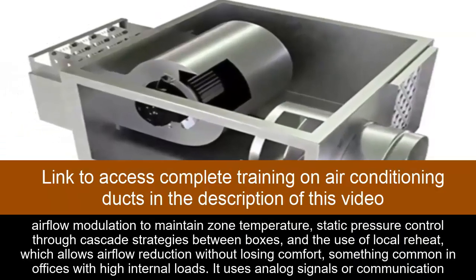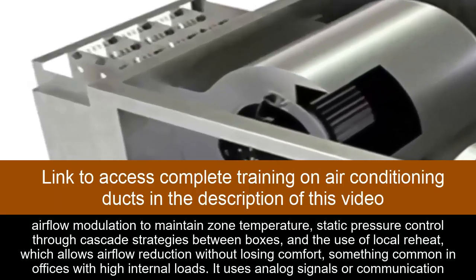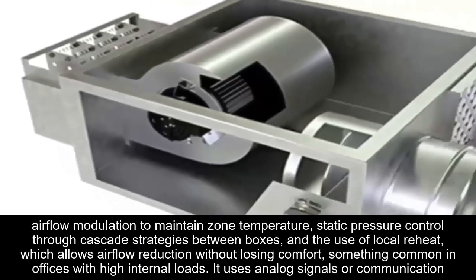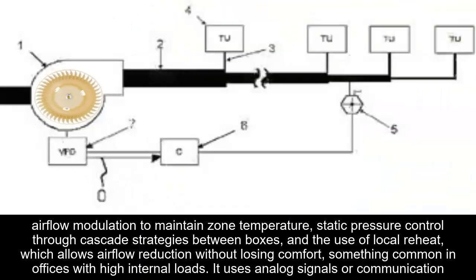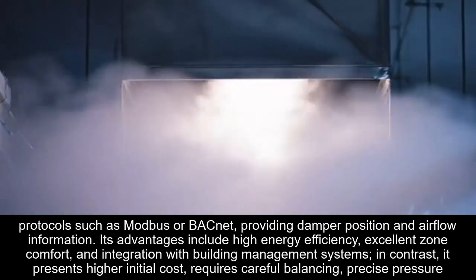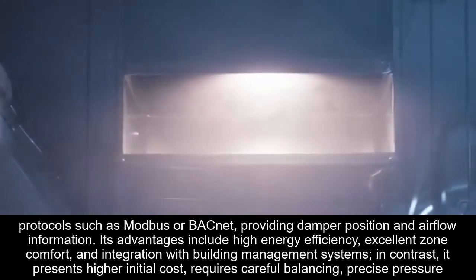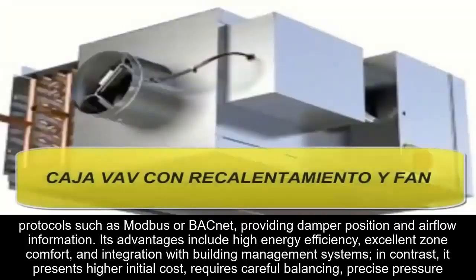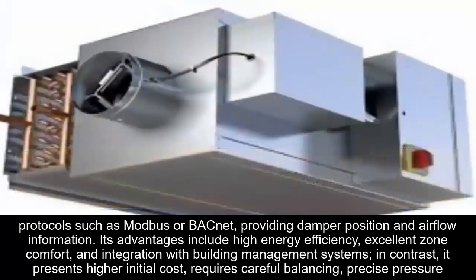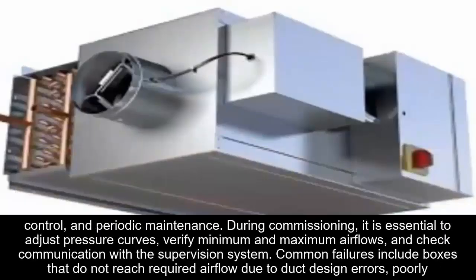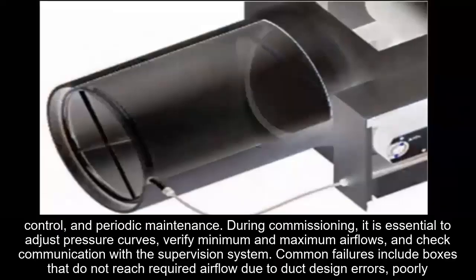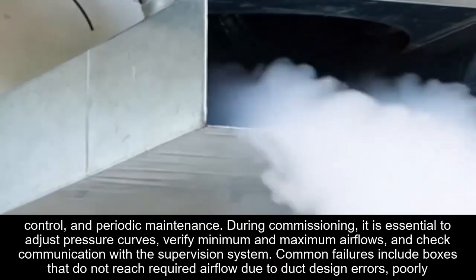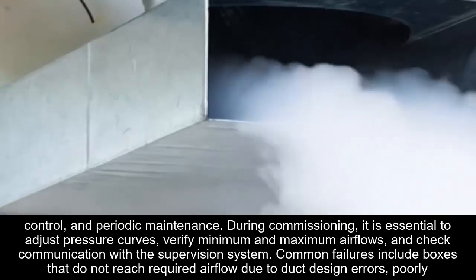Its operation may be based on direct airflow modulation to maintain zone temperature, static pressure control through cascade strategies between boxes, and the use of local reheat, which allows airflow reduction without losing comfort, something common in offices with high internal loads. It uses analog signals or communication protocols such as Modbus or BACnet, providing damper position and airflow information. Its advantages include high energy efficiency, excellent zone comfort, and integration with building management systems. In contrast, it presents higher initial cost, requires careful balancing, precise pressure control, and periodic maintenance.